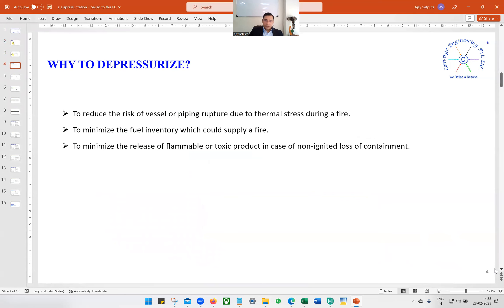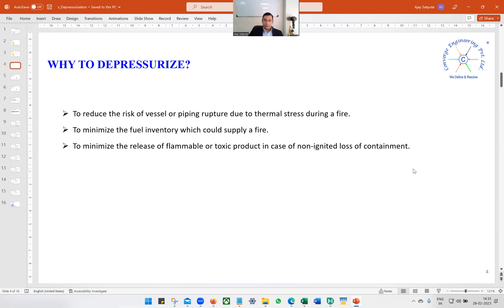Why do we depressurize? There are three reasons: to reduce the risk of vessel or piping rupture due to thermal stress during a fire; to minimize the fuel inventory which could supply a fire; and to minimize the release of flammable or toxic products in case of non-ignited loss of containment. These three reasons are straightforward and self-explanatory.